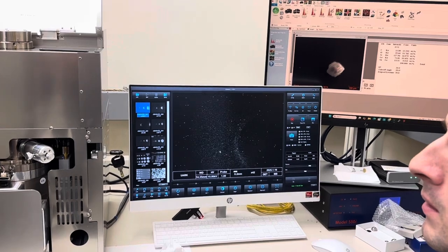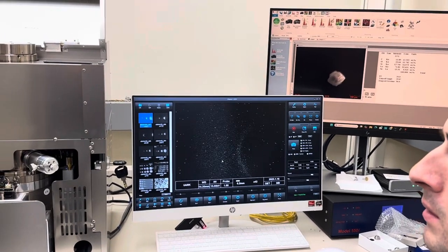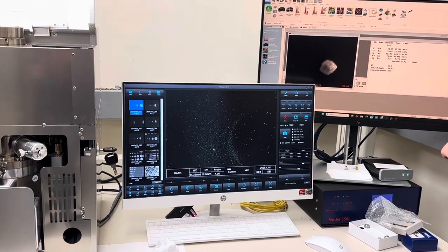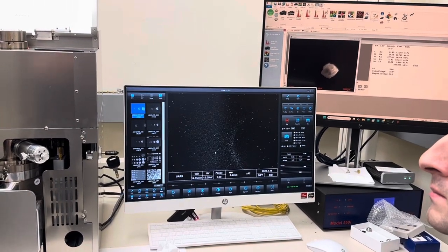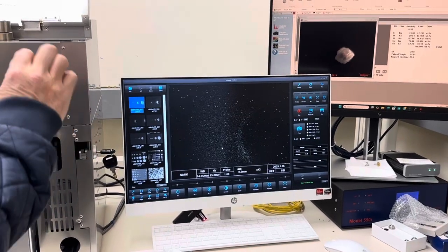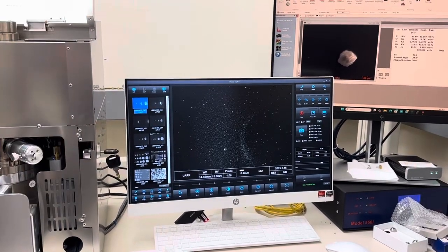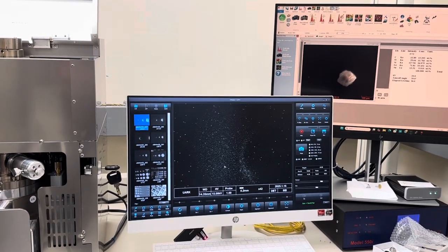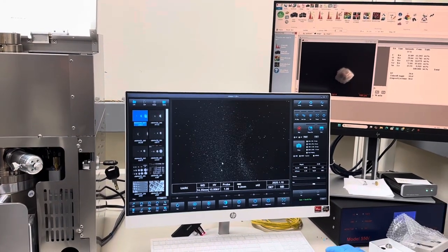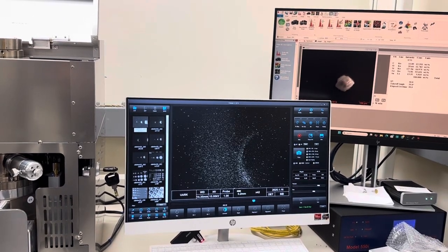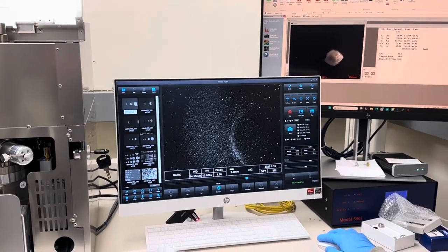When you introduce contrast, you're introducing voltage to a detector, and it's looking for any type of signal. So it's looking for beam, which it has, it's just not aligned, obviously, or not saturated. And so we see these dots. Because we're saturating the contrast, we see photomultiplier tube noise, which is normal. You can even give it more contrast. Even better. Great, so we even see a little bit more. Now left click your mouse.